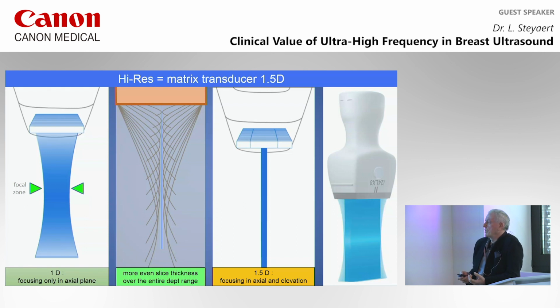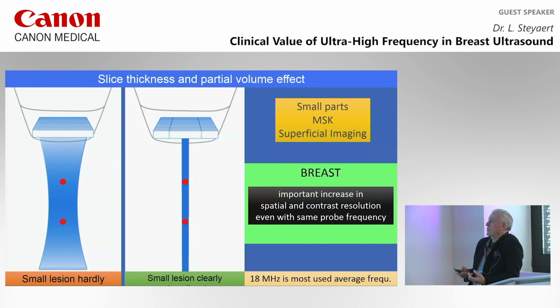And that is very important in breast imaging, for example, because we all know the partial volume effect. If you want to see very tiny structures in the breast, like the microcalcifications, it's very important. If they are much smaller than the slice thickness, you won't see them. You need a very thin slice thickness to have the resolution for very small lesions. And in the breast, this is as important as the higher frequency, because frequency mainly dictates the axial resolution, but the slice thickness is also very important to resolve these small things.